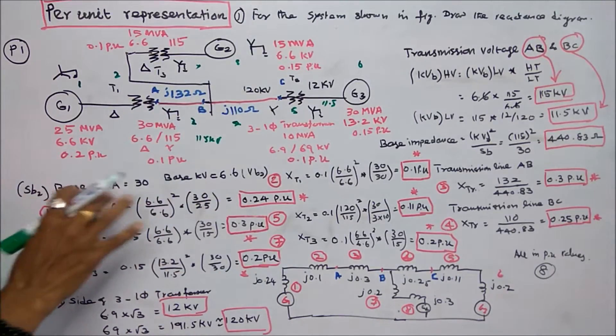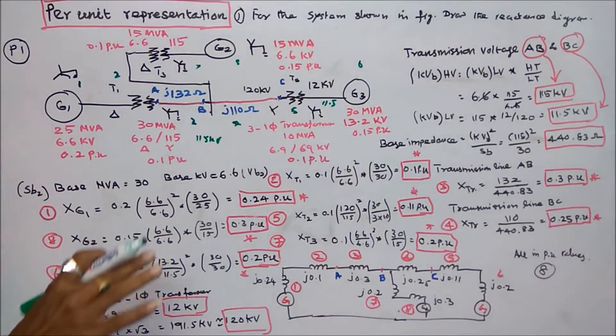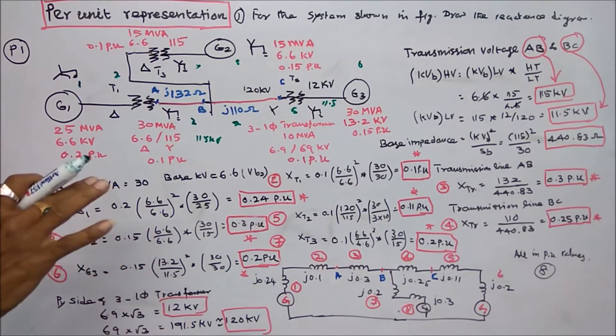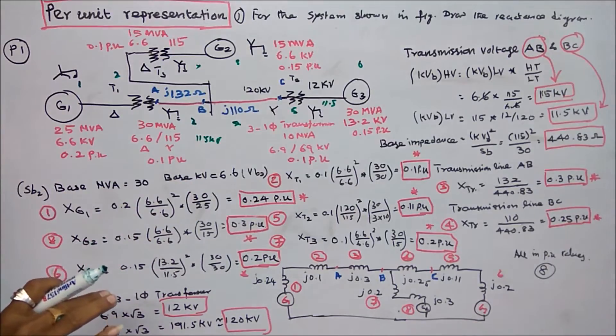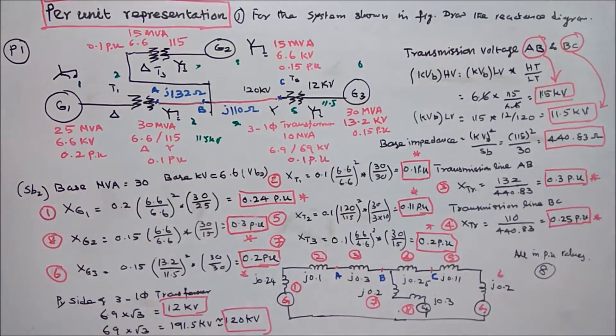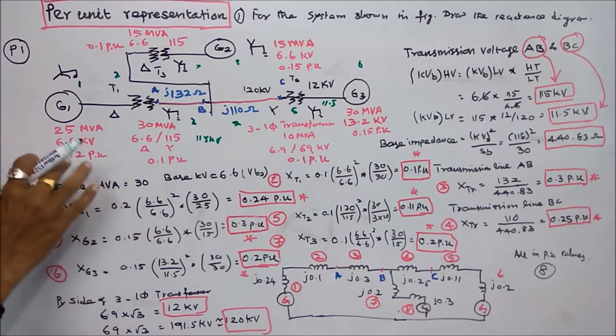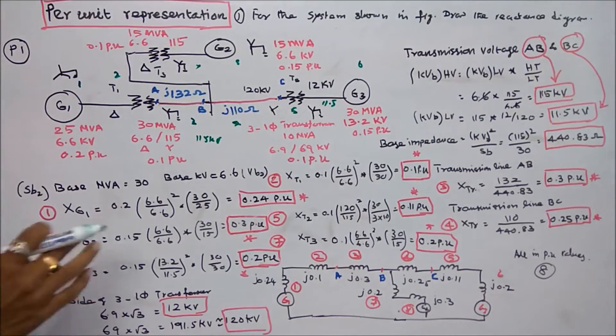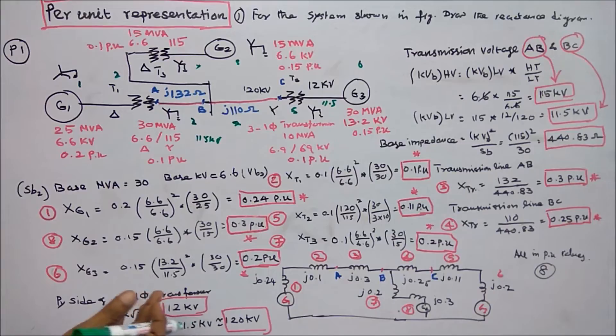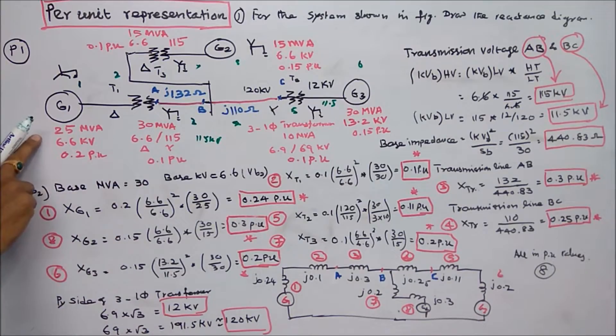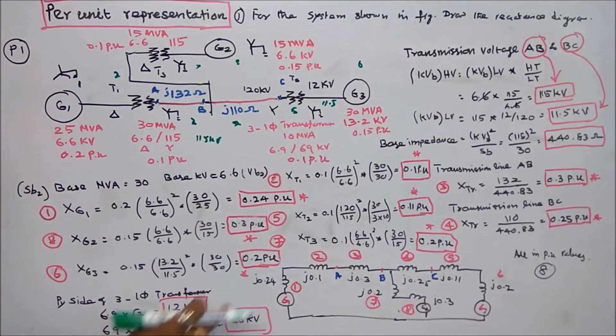The highest value is 30 MVA. So the first step is to choose base MVA = 30, base kV = 6.6. For generator 1, the per unit reactance is given as 0.2, so new per unit = 0.2 × (6.6/6.6)² × (30/25) = 0.24 per unit.